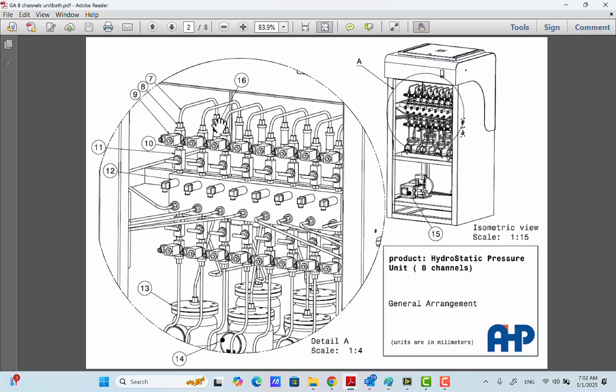water line. Be noted that the water needs to be deionized, clean, soft water, because the pressure unit has many elements inside it with very tiny holes. For example, solenoid valves have a very tiny hole inside, maybe 1 millimeter or 1.2 millimeter or less. In case of dirt coming into the pressure unit, it will cause you problems, and you need to open these valves and check valves to clean them, to remove the solid objects that come into the water and cause problems in the function of the solenoid valves and check valves. Cleaning of the solenoid valves is easy.